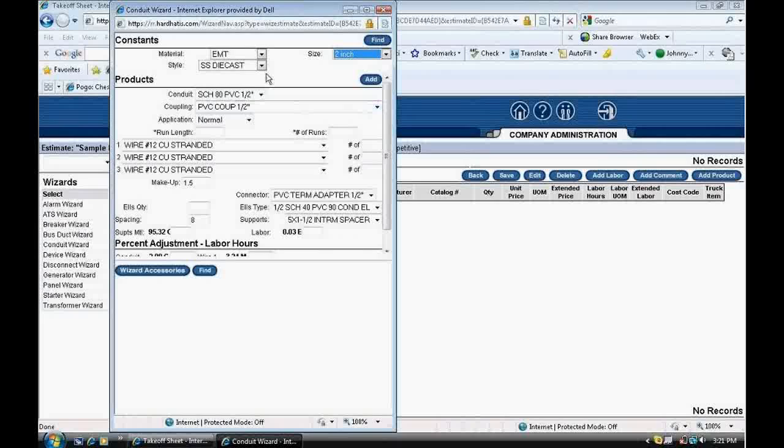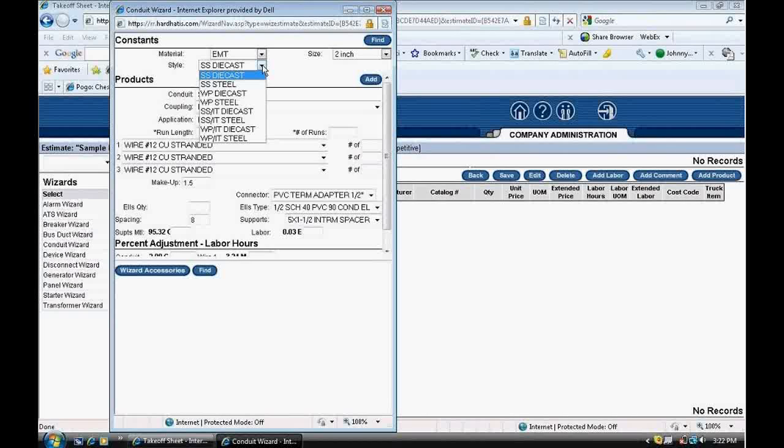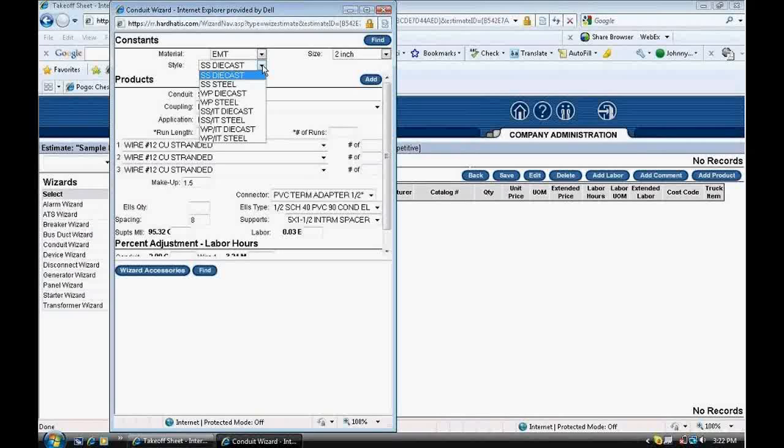Below the Size drop-down, it says Style. I'll click on that drop-down, and this setting allows me to choose what type of EMT fittings to input into the program. Many types of EMT fittings are available to select from on the drop-down list. Let me explain. There's four different types. They're either steel or die cast. SS means set screw. WP means weatherproof, which are compression fittings. SSIT means set screw insulated throat. And WPIT means weatherproof or compression fittings insulated throat. For this example, we'll use SS die cast.